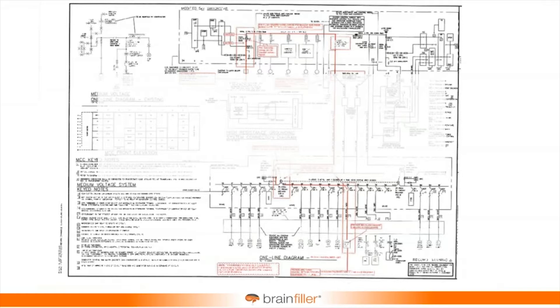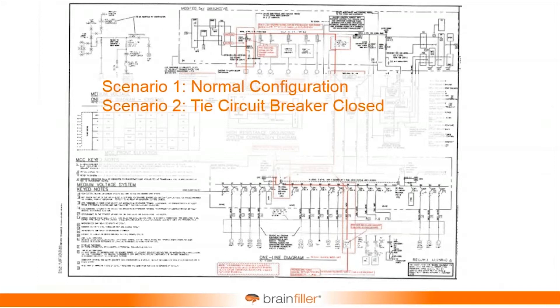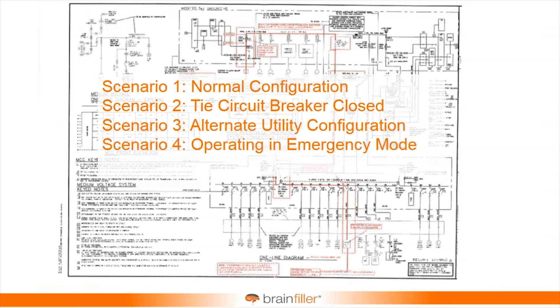And suddenly the question becomes, if I'm going to perform arc flash calculations, I want to base this on the normal configuration — the normal short circuit current, the normal configuration of ties open or closed. And then alternative scenarios: maybe the tie breaker was normally open, and now what happens if it's closed? Maybe an alternative utility configuration, emergency mode. If you have larger complex systems, you can have all kinds of different scenarios.